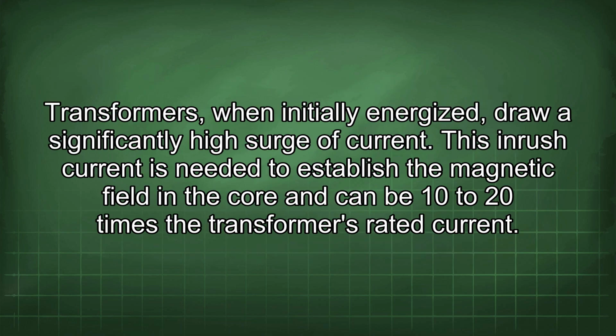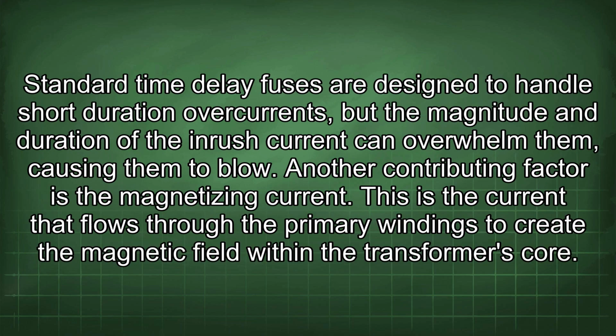Transformers, when initially energized, draw a significantly high surge of current. This inrush current is needed to establish the magnetic field in the core and can be 10 to 20 times the transformer's rated current. Standard time delay fuses are designed to handle short duration overcurrents, but the magnitude and duration of the inrush current can overwhelm them, causing them to blow.